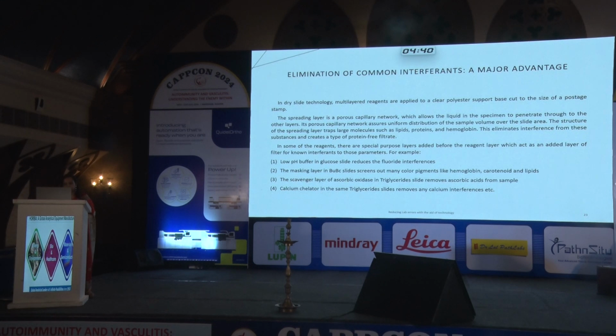The scavenger layer of ascorbic acid oxidase in the triglyceride slide removes ascorbic acid from samples, which is important in patients having vitamin C supplements or having lots of citrus fruits. Calcium chelator in the same triglyceride slides remove any calcium interference.